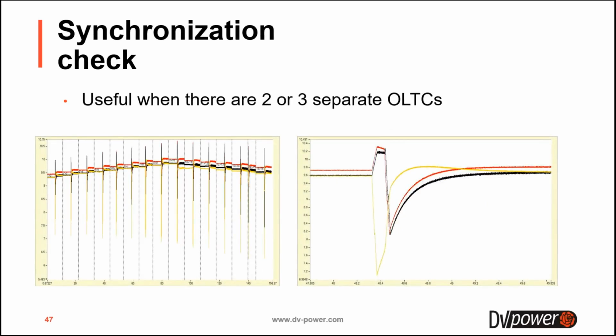Another thing that you can do with DVtest is check the synchronization between phases. This is very useful when you have a transformer that has 2 or 3 separate OLTCs. For very high voltages, 220 kV, 400 kV and above, you'll probably have a transformer with multiple OLTCs.